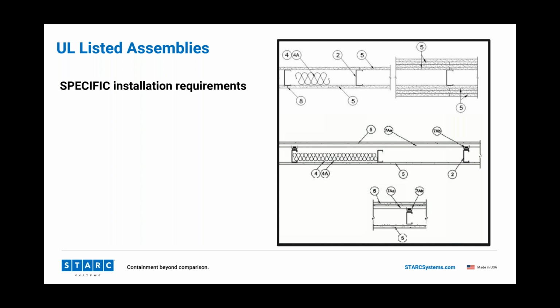The contractor had somebody building the 2-hour wall on one side and somebody building the 2-hour wall on the opposite side, and they were building two different 2-hour walls. Both were approved UL listed assemblies if built in uniformity. However, because they were building it differently, it had never been tested that way. There was no proof that that was actually a 2-hour barrier anymore. So it's very important that you follow the installation requirements associated with UL listed assemblies.